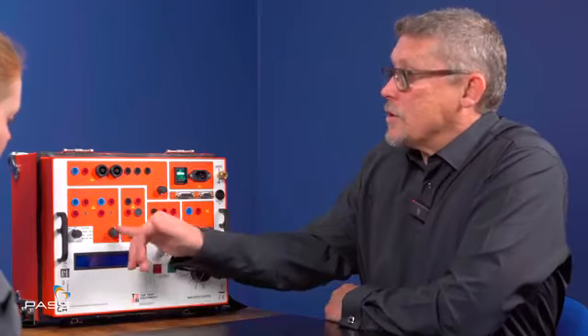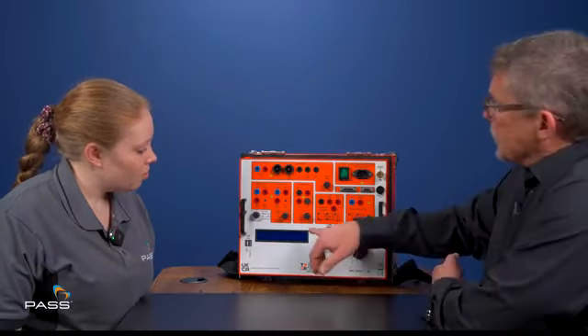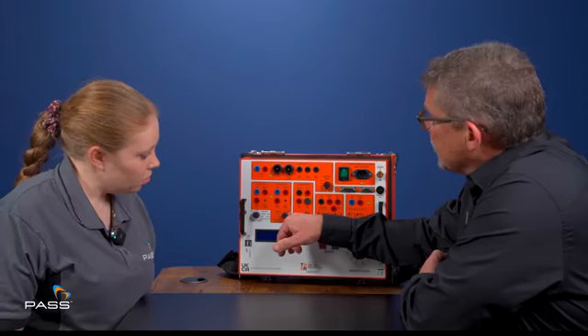We also use the pulse if I'm doing a circuit breaker test, instantaneous break on a circuit breaker, because if I'm outputting 160 amps and the breaker doesn't operate, I don't want to cause damage to the breaker by putting too much current through it for too long. So we can limit that to 200 milliseconds. And the very last position we have on here is the aux AC.